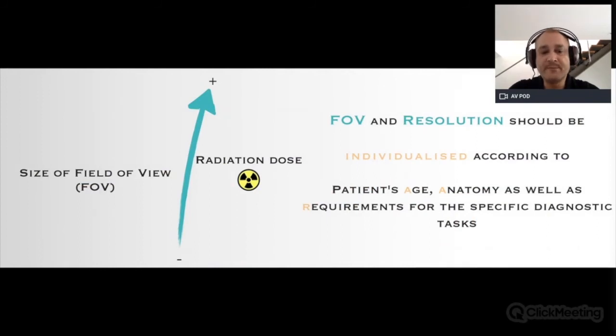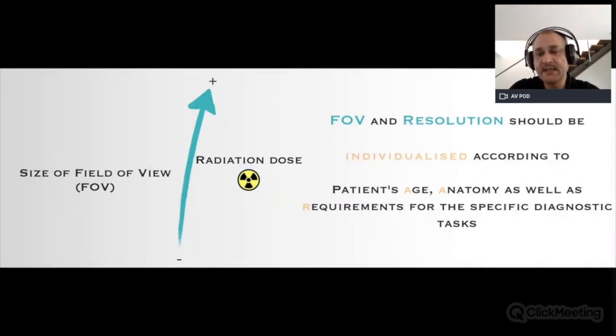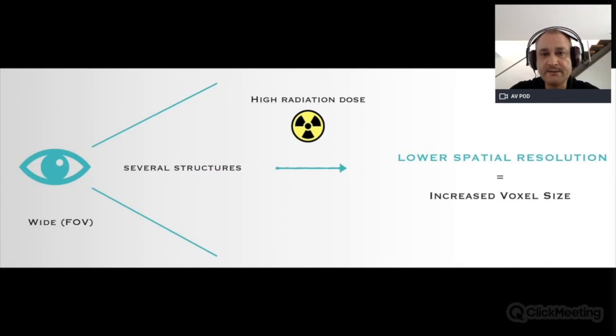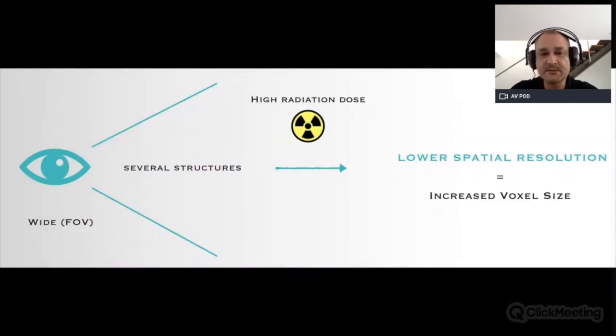When we have a bigger field of view, the radiation is higher. We must adjust the field of view according to the patient's age, anatomy, and the specific area of interest. For a wide field of view covering both upper and lower jaws, the radiation dose is higher, so it is wise to opt for a lower spatial resolution to avoid unnecessarily harming the patient.